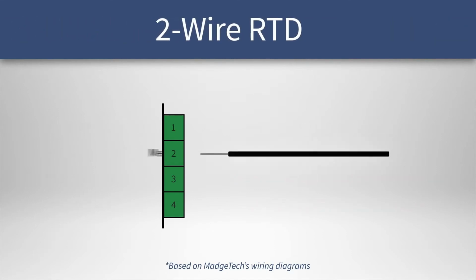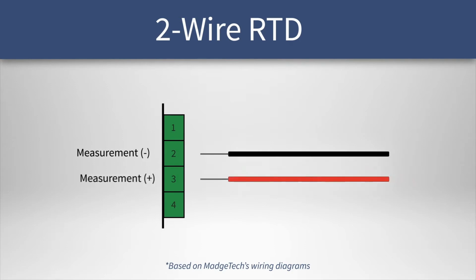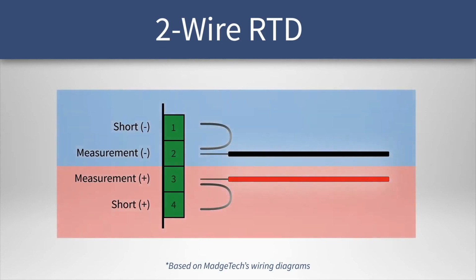Our second example is a 2-wire probe. In this example, a black wire should be connected to terminal 2, and a red wire should be connected to terminal 3. A small wire should be used to short terminal 1 to terminal 2, so they are electrically connected. And in the same way, a small wire should be used to short terminal 4 to terminal 3, so they are electrically connected. Take care that the shorting wires do not allow a short between the positive and negative terminals. Terminals 1 and 2 should be electrically isolated from terminals 3 and 4.